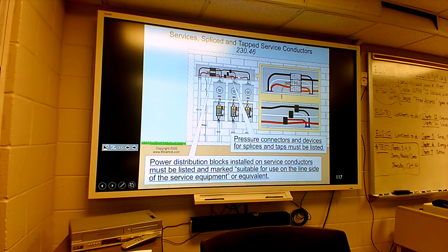If you notice up here, they got a thing that lets you splice into a wire and do a tap off for something else. So services, spliced and tapped service conductors. Pressure connectors and devices for splices and taps must be listed, which means it's got to be something store-bought that's made for it, that's approved by UL. It has to be an approved device that won't damage the wire when it taps into it, when it cuts the insulation. So things like that, they'll actually pierce in through the insulation and they'll give you a tap without actually cutting the wire. It actually cuts it for you.